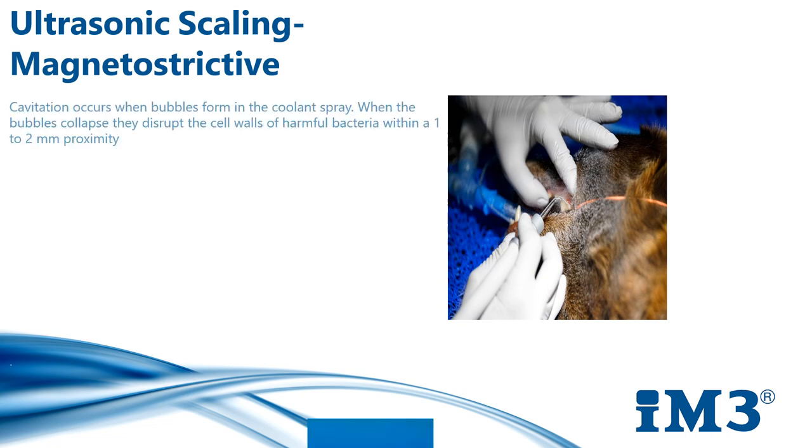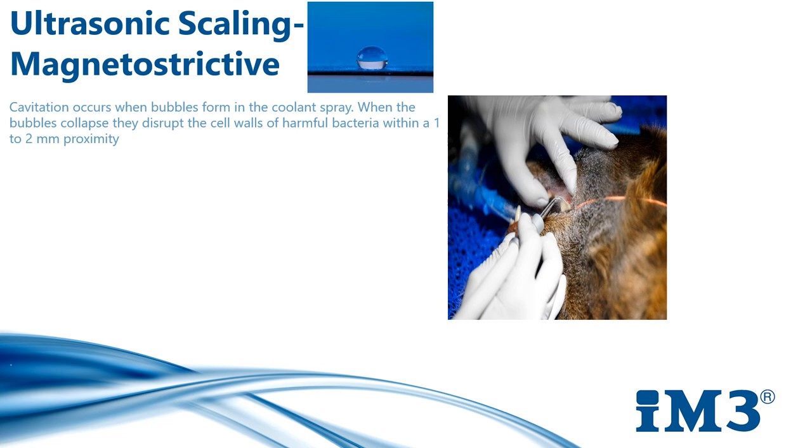There are two types of ultrasonic scaler we'll discuss today: the magnetostrictive and the piezo. Ultrasonic scalers operate at a high frequency of between 20 and 50 kilohertz. When we use an ultrasonic scaler, water lavage helps to remove plaque and wash away debris in the periodontal pockets. Cavitation also occurs when bubbles form in the coolant spray. When these bubbles collapse, they disrupt the cell walls of harmful bacteria within a one to two millimeter proximity, promoting improved dental hygiene particularly in deep subgingival pockets.